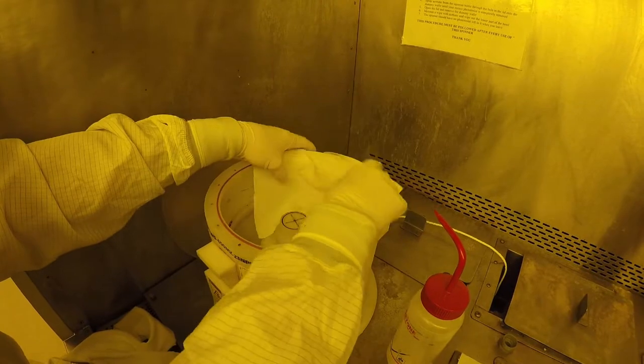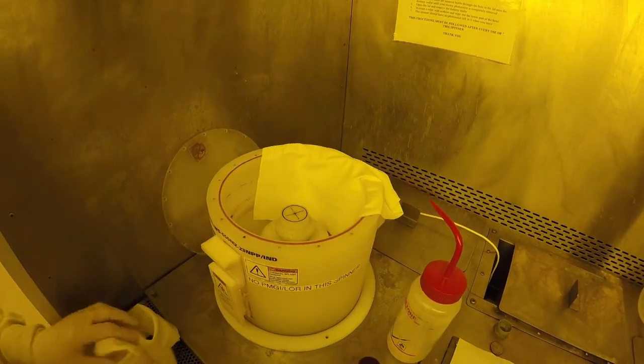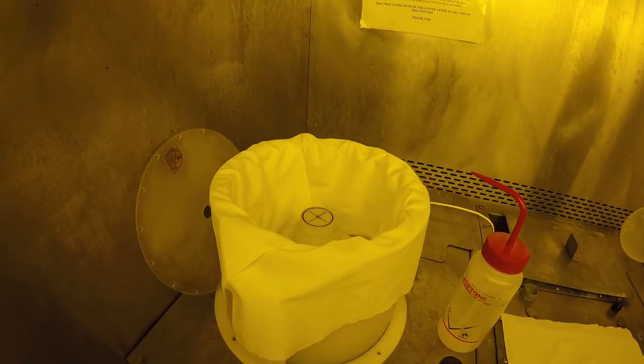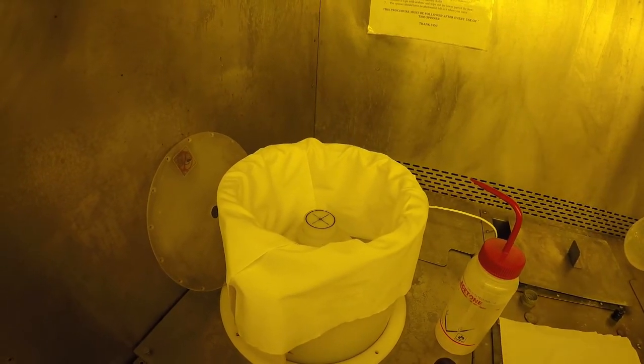There are a number of spinners. Some are dedicated for particular types of photoresist and solvents. Please pay attention to all posted signage. To use a spinner, first sign into the log sheet, then line the spinner bowl with foil or wipes. Now the spinner is ready for your recipe.